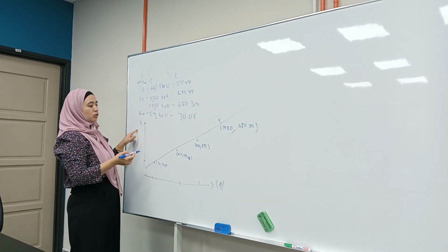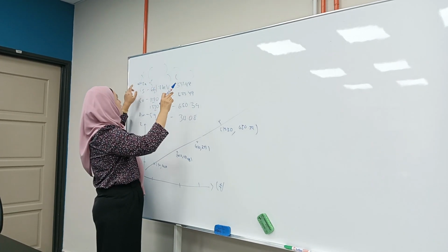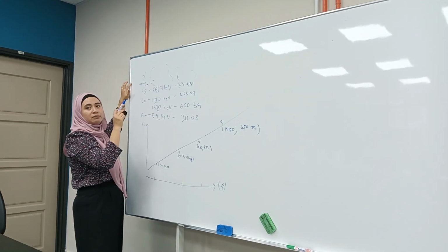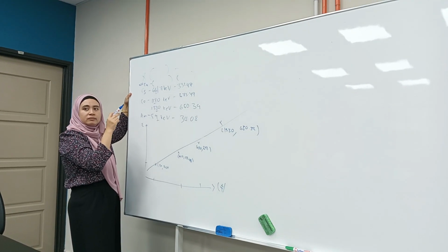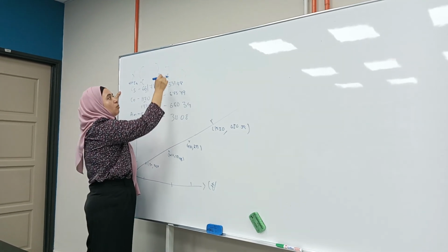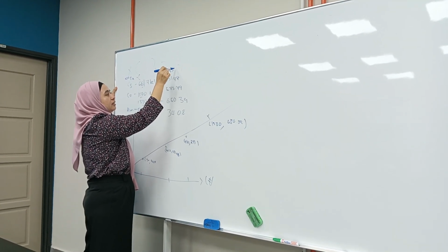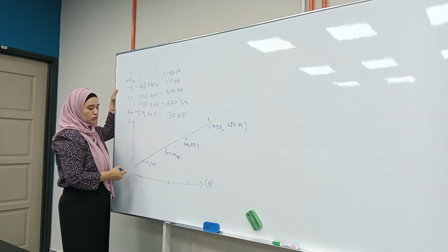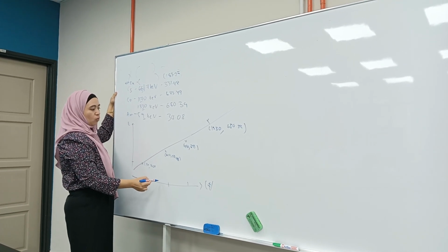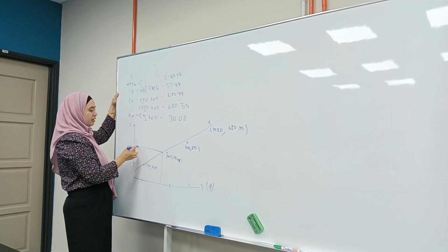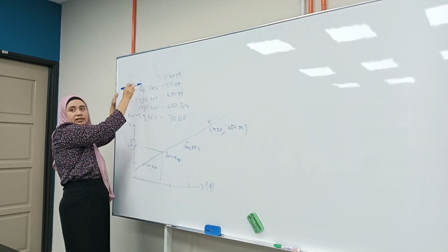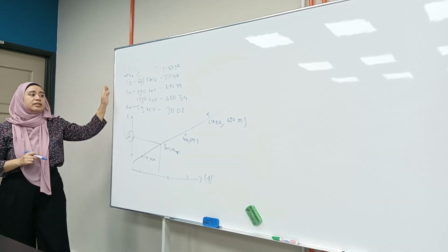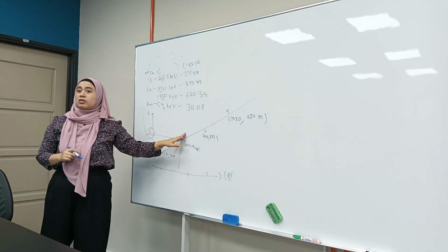So you now go to the channel number. What was the energy for barium earlier? The channel number for barium? 183.27. Now go to your Excel curve, go to 183 and identify the energy and check if the energy is correct, so that you can validate the calibration curve that you have plotted.